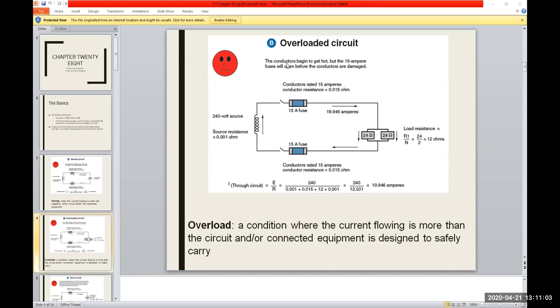Now, what happens here when you get an overloaded circuit? How does this work? The thing to think about is that it's an overload, and that means the current has to spike, and it has to spike for a little bit of time for these things to work. Because when you first turn things on, there's a spike in current pull, like when you turn a motor on. It'll jump up and over, but it settles down really quick. So usually these fuses and circuit breakers are rated with a little bit of time, a couple of seconds, of course, but there's a little bit of trip time to them.